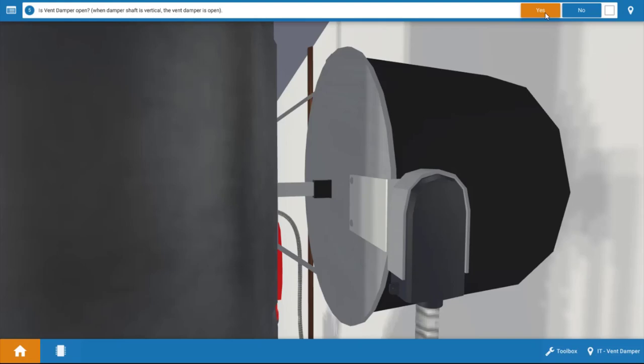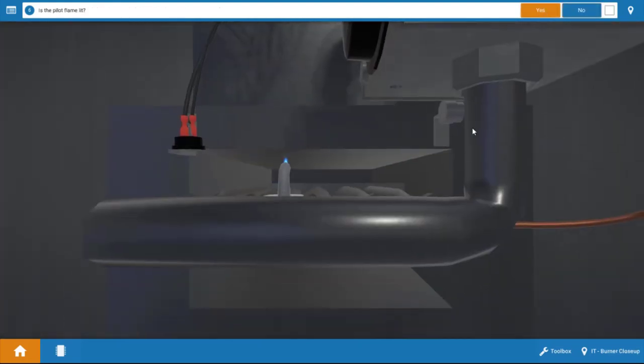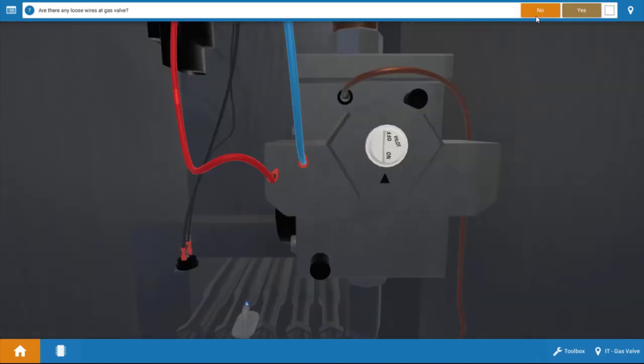Now, it does have an end switch that could still be faulty, but we're going to click Yes for now. Our pilot is lit. We've already established that.